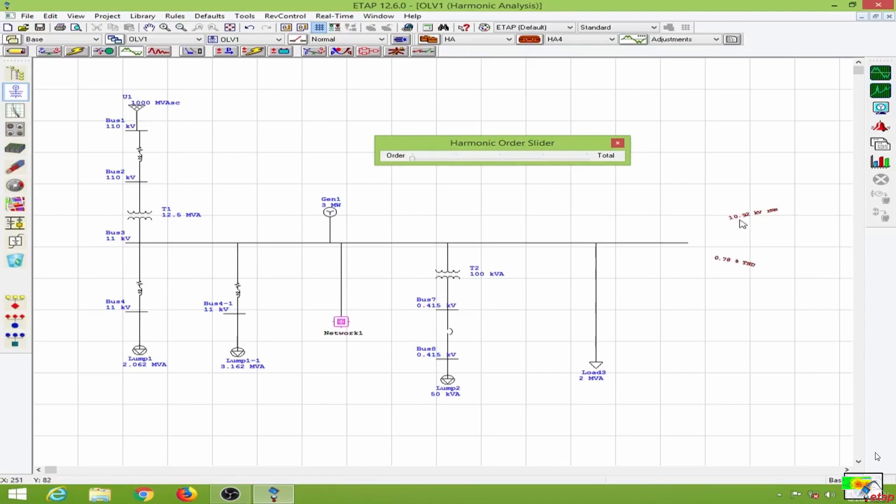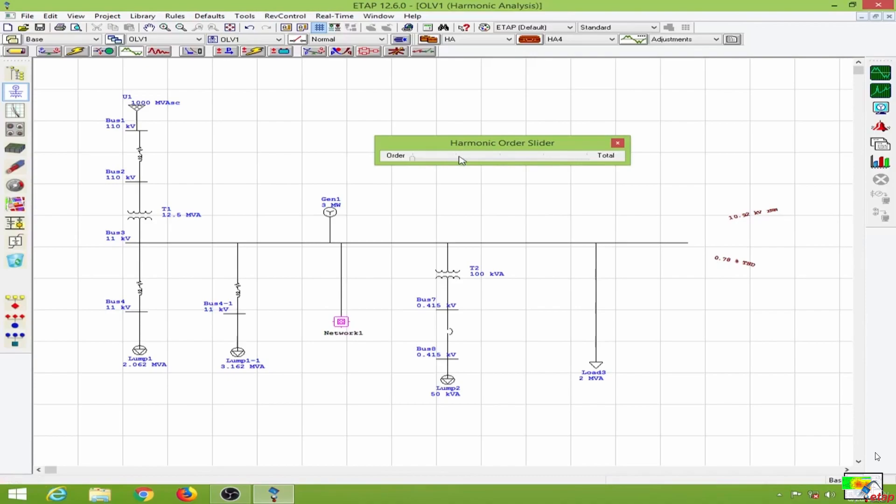This is about 10.92 kilovolt, and the total harmonic distortion is about 0.78 percent. When I slide the harmonic order, the first harmonic is about 10.92, there is no third harmonic, the fifth harmonic is 0.07 kV, and this is the seventh harmonic.